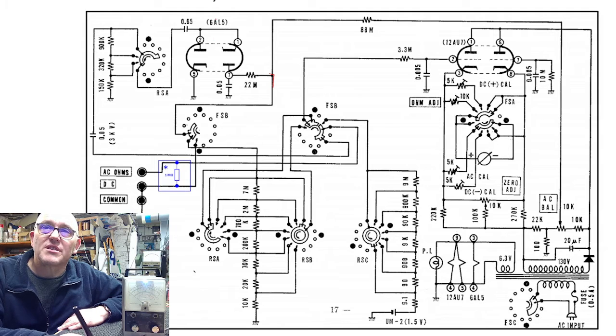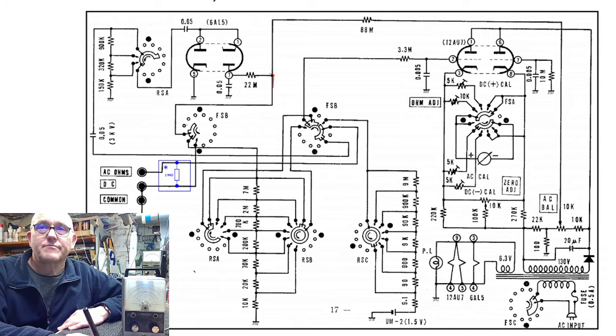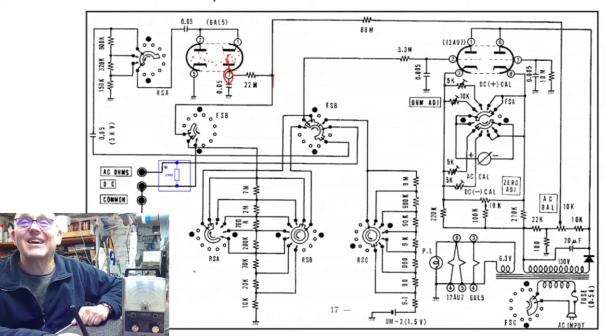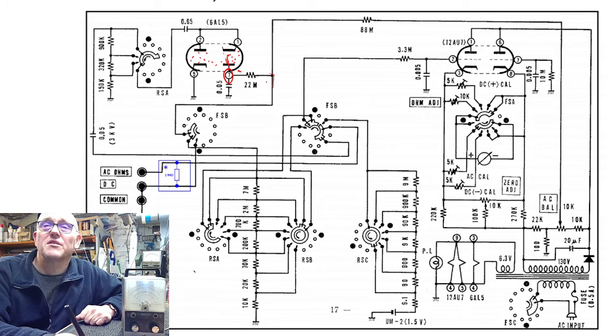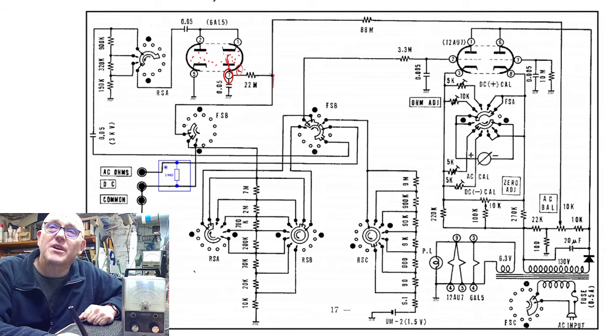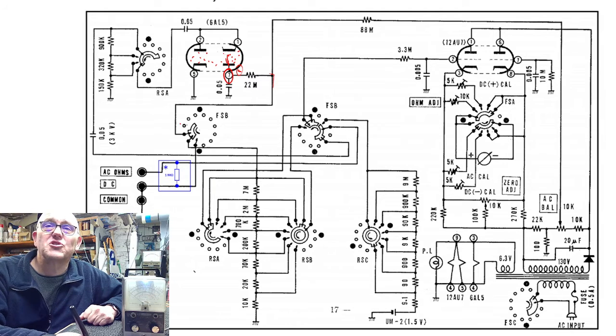There's another problem that arises with this 6AL5 rectifier. When we switch on the meter, we end up with the heater element of the 6AL5 heating up these cathodes, and we get a cloud of electrons flying around inside of the tube willy-nilly. Let's say with zero input. I'm not talking about any input over here. These electrons, as they are flying around, will collide with the anode on the outlet on pin 7 and create a negative charge to come and sit over here. A very small negative voltage. Let's say it's minus 0.1 volts, minus 1 volt, something. But a very small negative voltage will naturally come and sit over here. This will then skew the multimeter readings. It will deflect the needle in a negative direction and it won't sit at zero.